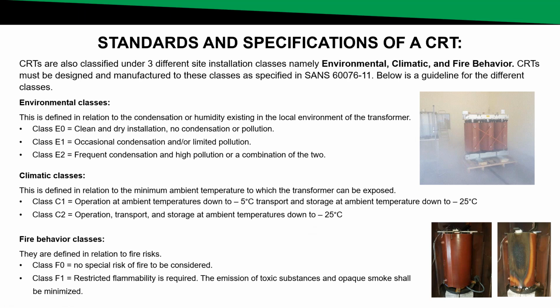The fire behavior class, this is the resistance of the transformer to fire and fire risk. So the class F0 is no specific risk of fire to be considered. So there's no exposure of fire or risk of fire to the transformer. Class F1 means there is a risk to the transformer through fire. However, the transformer must be able to suppress that fire, and the toxic gases and smoke should be minimized. As you can see on the pictures, there's a typical example of a transformer being tested to comply to the environmental classes and climatic classes, and another one where you can actually see where the transformer is tested to see if the transformer actually burns.